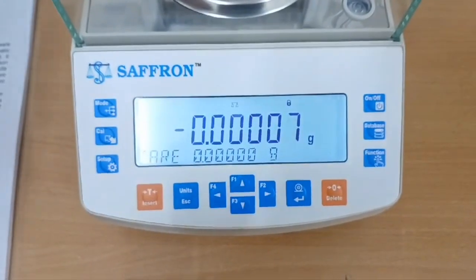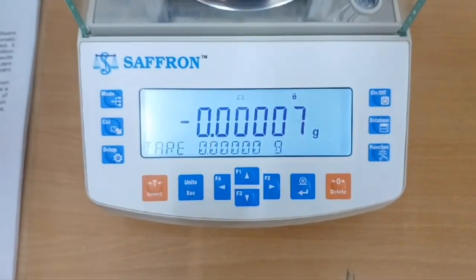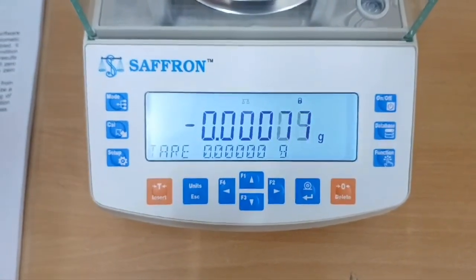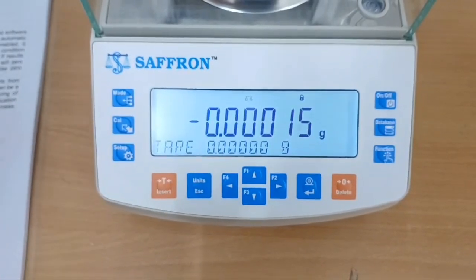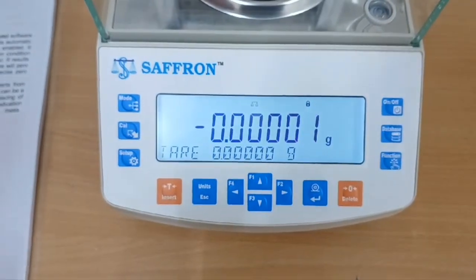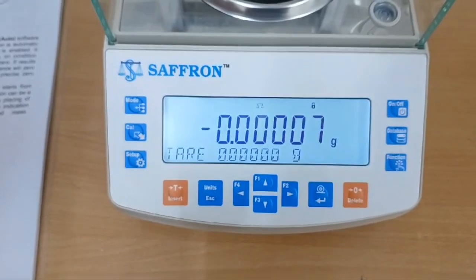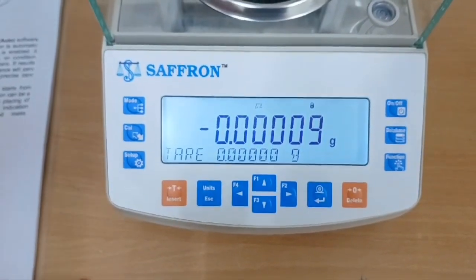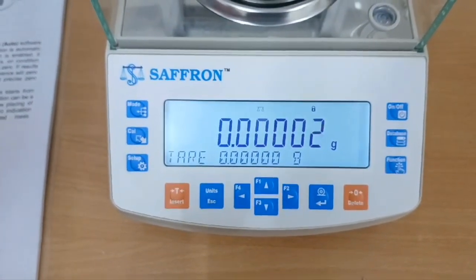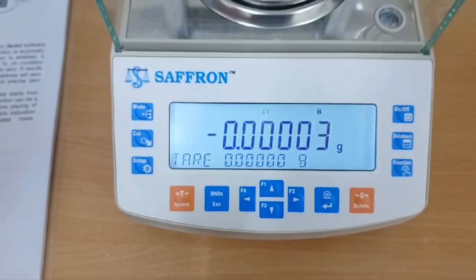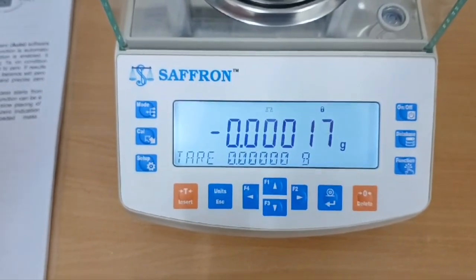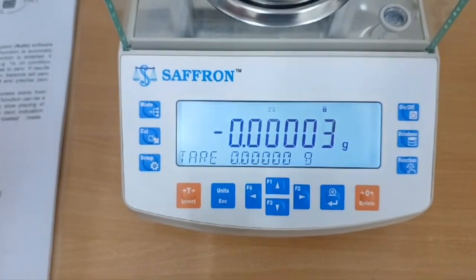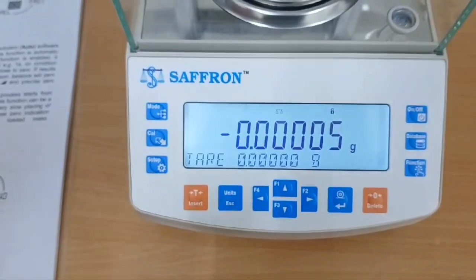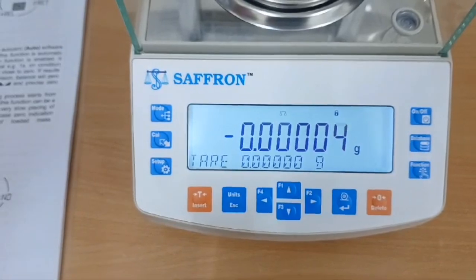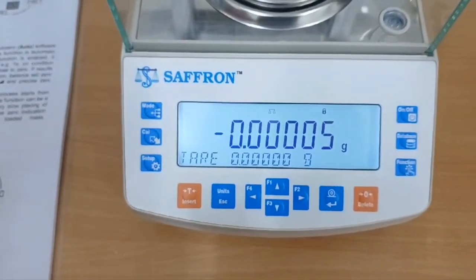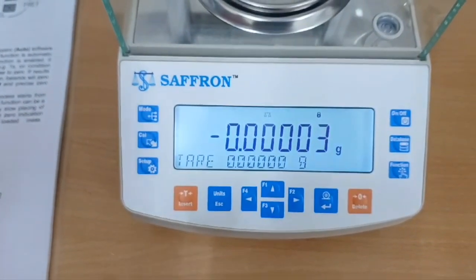In order to ensure that the balance has precise calculations, there's an auto-zero software or parameter that's been introduced. This allows control and correction of the zero indication on the machine. So when the function auto-zero is enabled, it compares the balance indications at the declared time interval on condition that the weighing pan is unloaded and the display indication is close to zero. This ensures accurate readings can be taken. We'll now show you how to make sure that the auto-zero function is on.